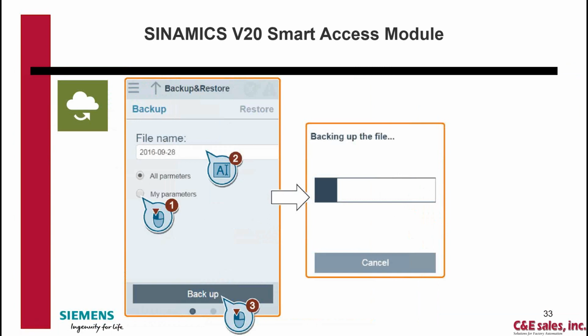Then the last menu we're going to talk about is backup and restore. The backup icon here generates a default file name of the date. You can change that to give it more meaning. You can back up all parameters or my parameters, and then say backup, and it's going to back it up onto this Smart Access module, which can hold 20 parameter sets.